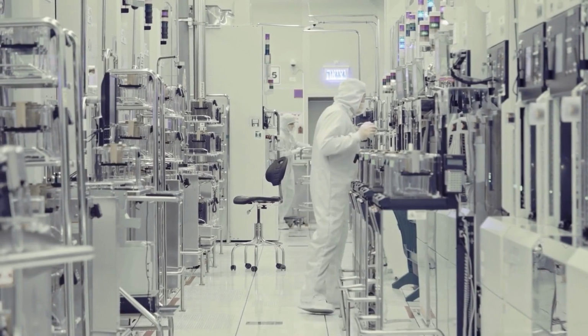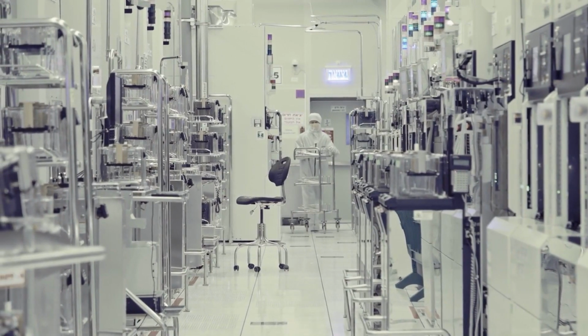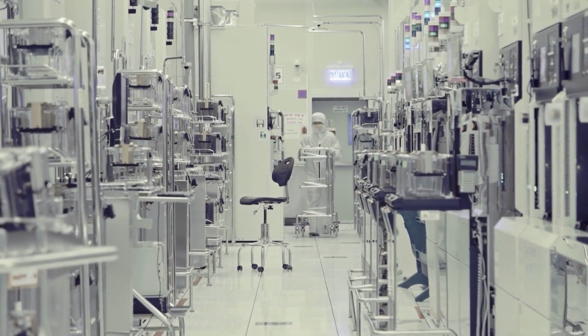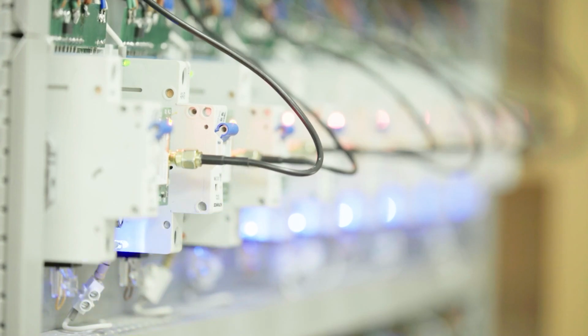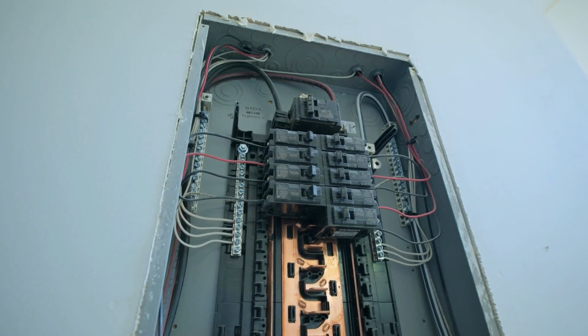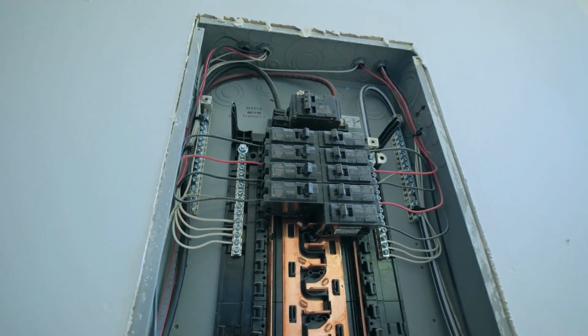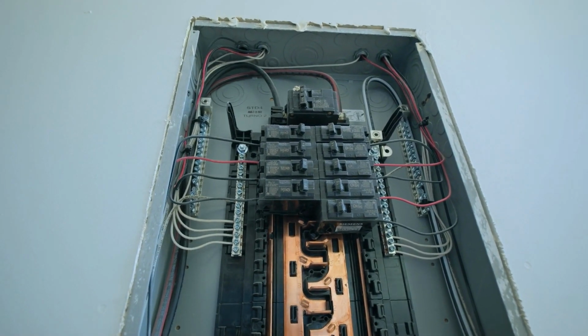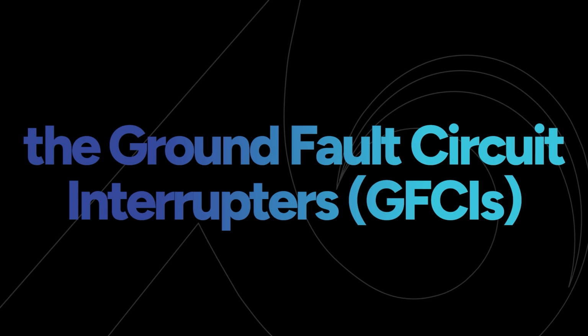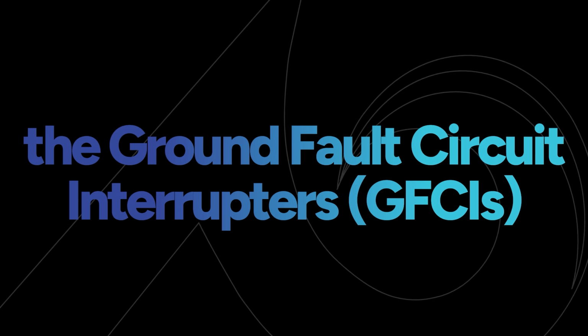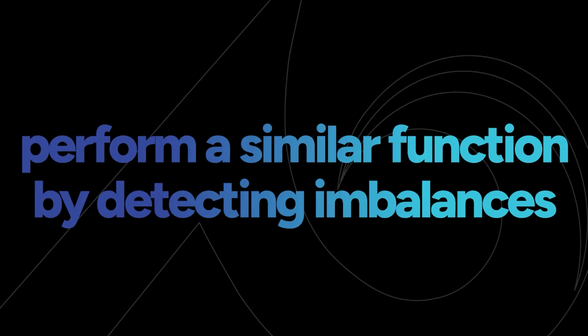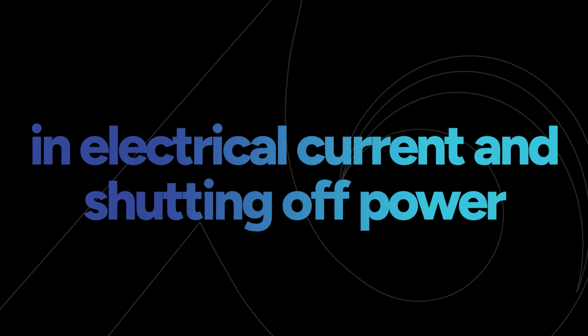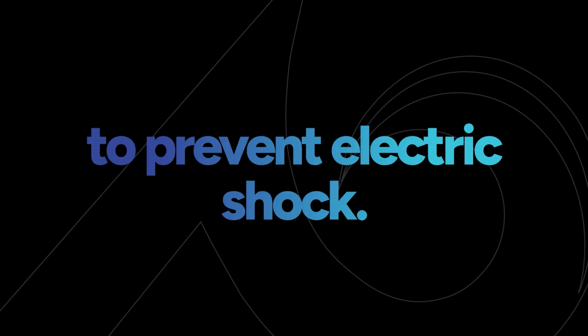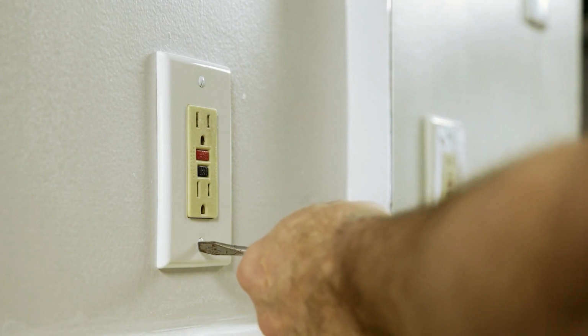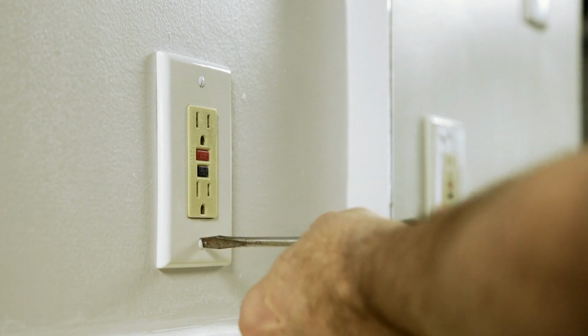Speaking of protection, some circuit protection devices add that extra layer of safety to laboratory workers. Take, for example, fuses protect circuits by breaking the circuit if the current exceeds a safe level. Then there are circuit breakers that automatically cut off electrical flow when they detect an overload or short circuit. Moreover, the ground fault circuit interrupters, or GFCIs, perform a similar function by detecting imbalances in electrical current and shutting off power to prevent electric shock. It's imperative that GFCI outlets be placed next to sinks and water basins for further protection.